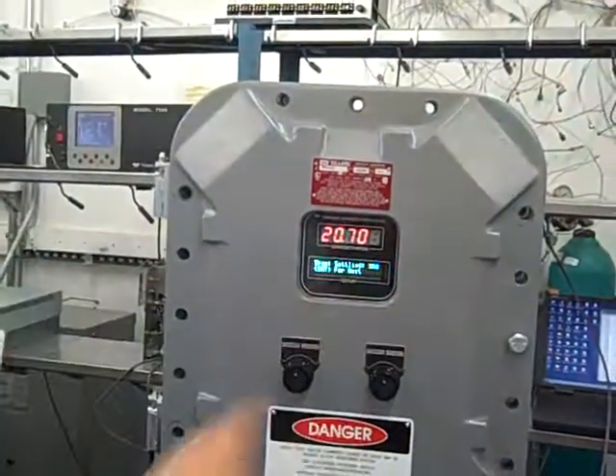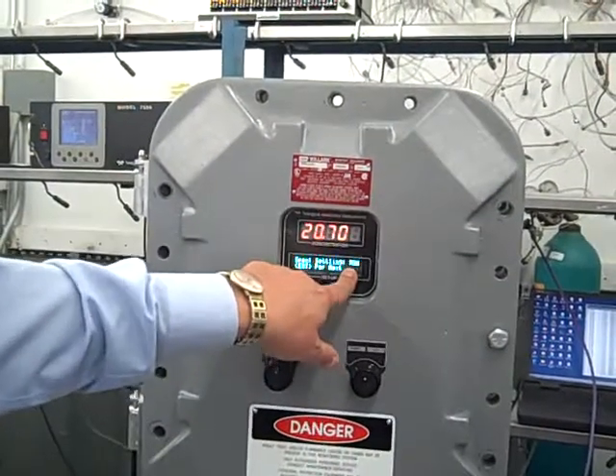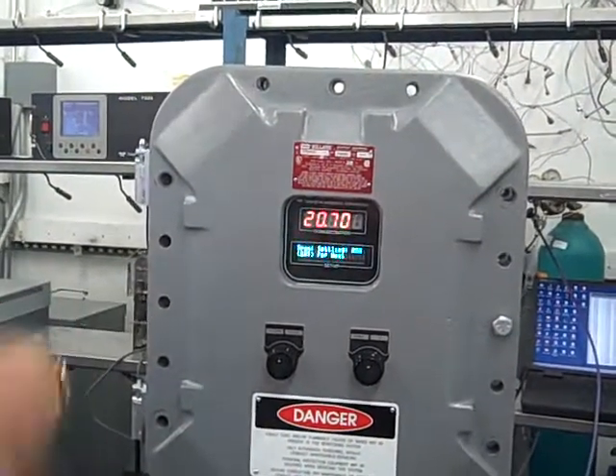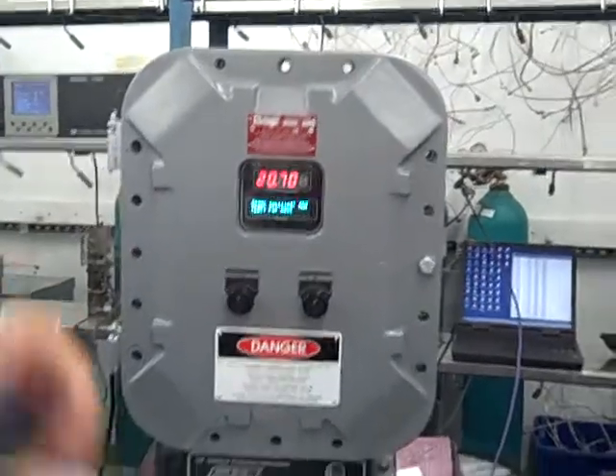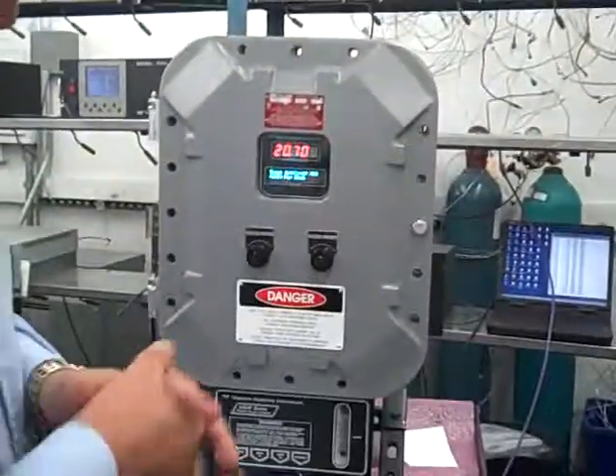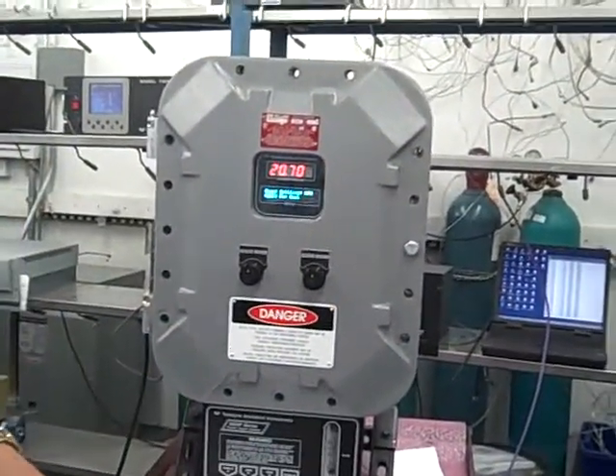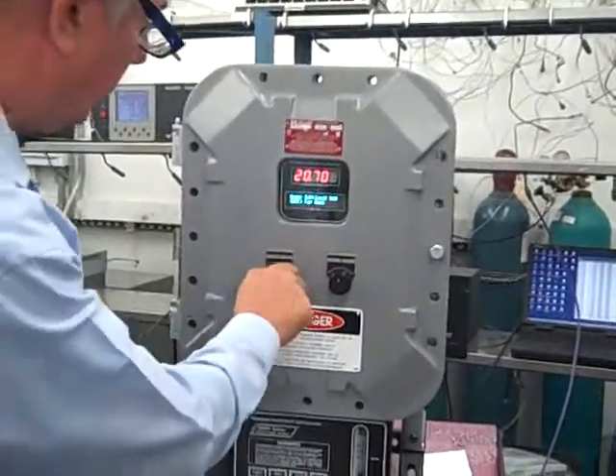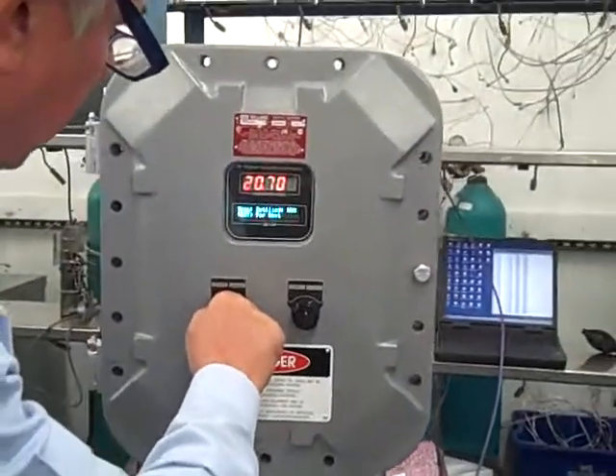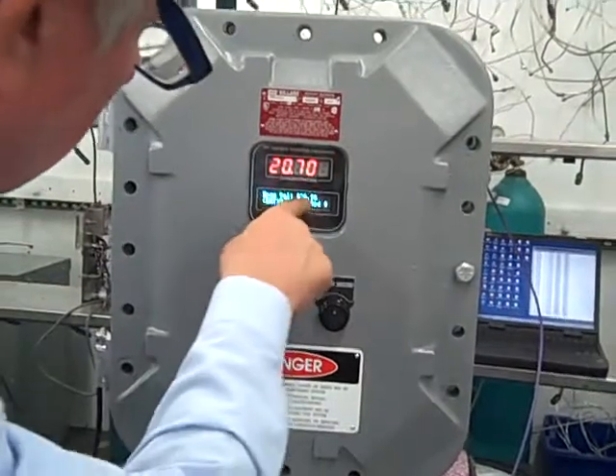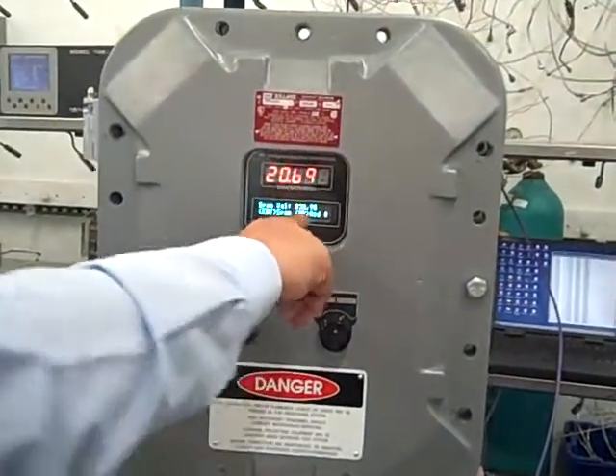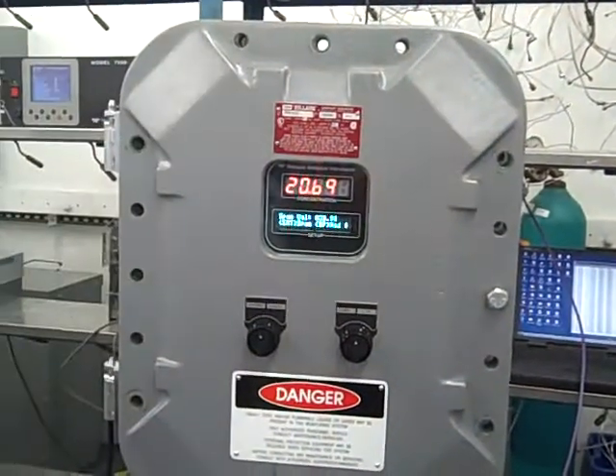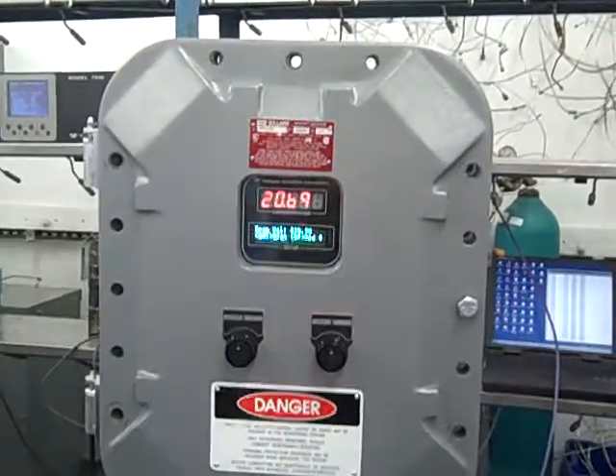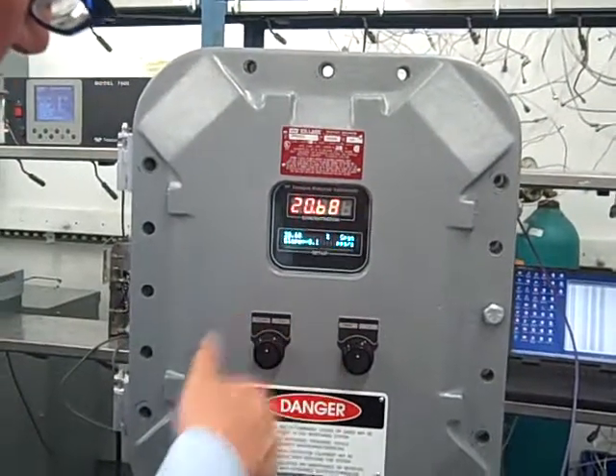Okay, now we have the choice between manual or automatic span. Manual span means you determine when the reading's stable. Automatic, auto, means the computer determines when it's stable. I prefer to use manual, so I'm going to go ahead and do that. I'm going to push enter. And now that's the span concentration, which is 20.9, which is a concentration that we have in open air. You see it reads 20.6. So we're going to go ahead and accept that, say yes.